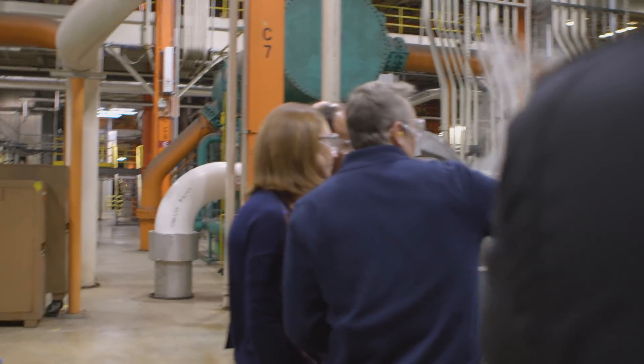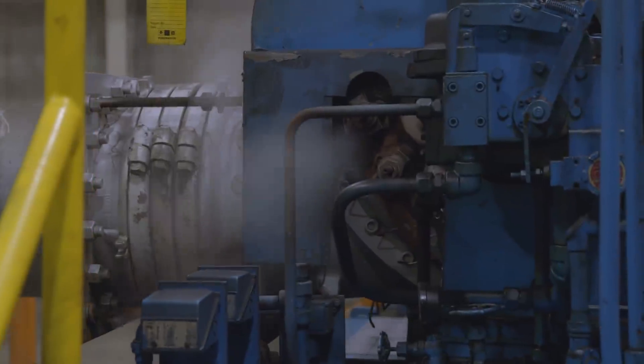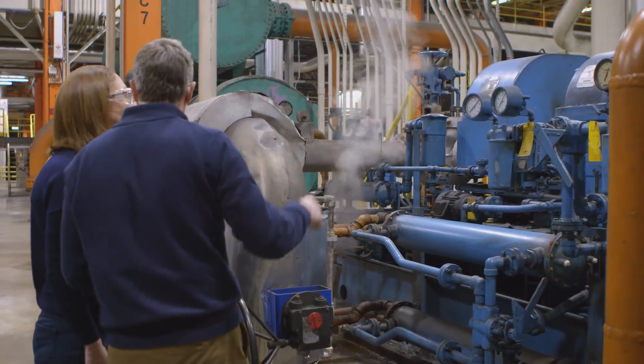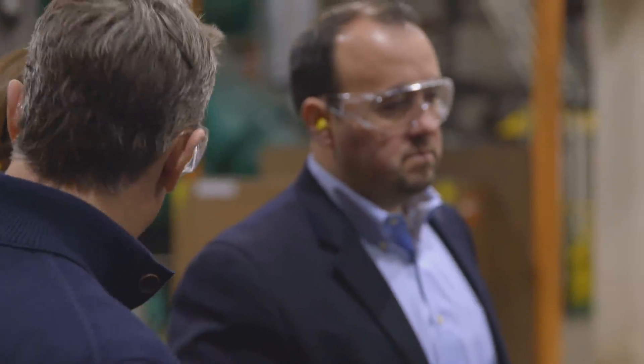Safety glasses and earplugs. A good practice on their valves is they should have some match marking to show what the normal range is. This may be controlled by their energy management system, but if it's a manual operation it's really hard to know what normal is. What I'd recommend is that they have some match marking for all of their manual gauges over here.